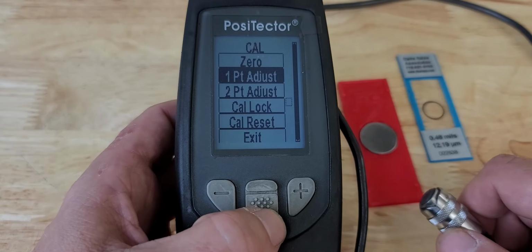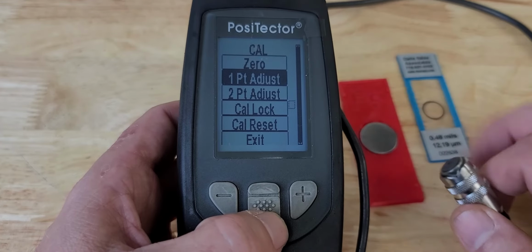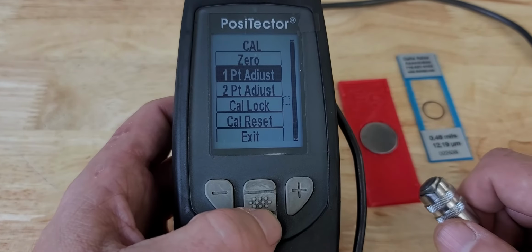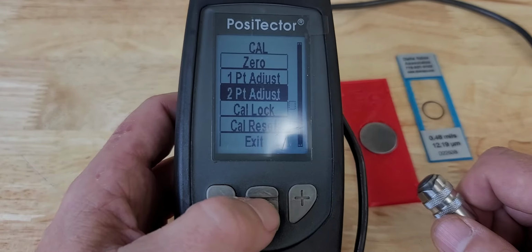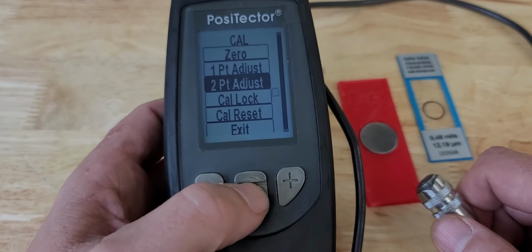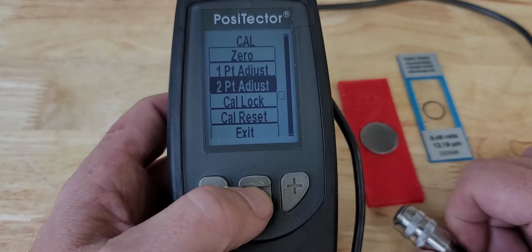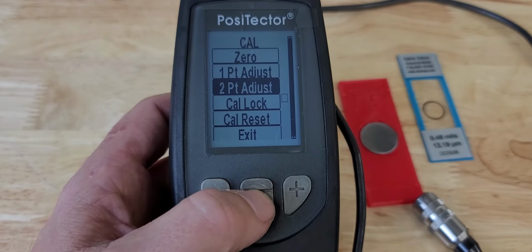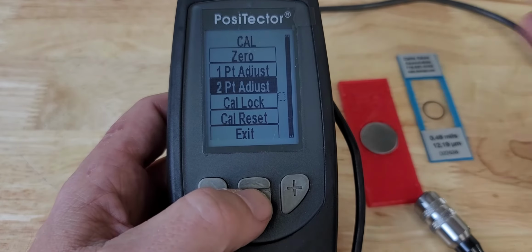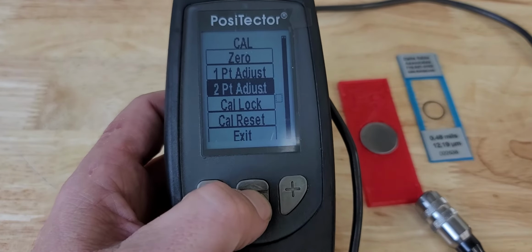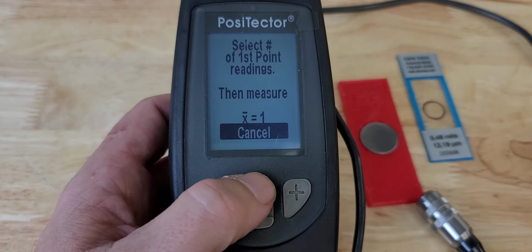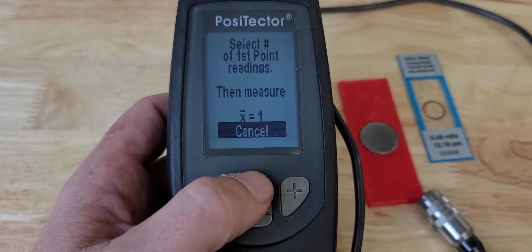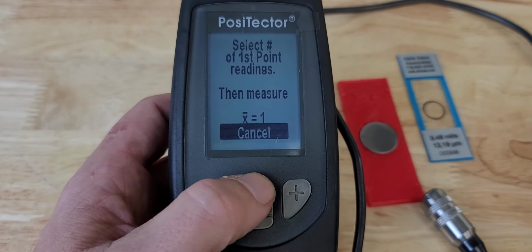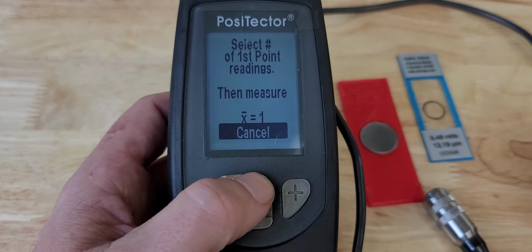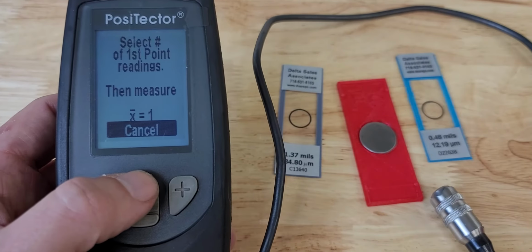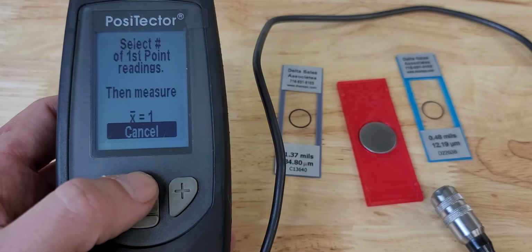We do a 1 point adjustment where we would just use one standard, but as always, I highly recommend you do a 2 point adjustment, and that is going to really dial in your calibration with a low and a high value. You want those low and high values to really bookend the range that you're looking at. Today our hypothetical range is going to be somewhere between 0.5 mil and 1.5 mils.